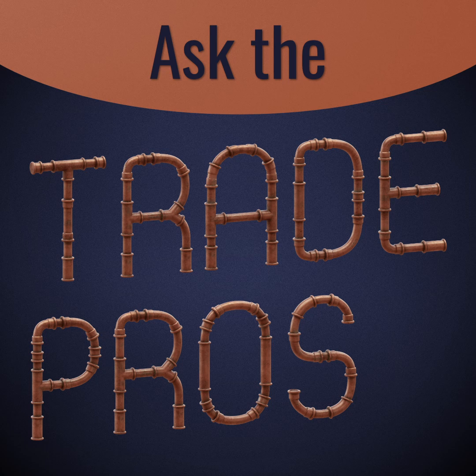So we strongly recommend that you be aware whether you have double taps. Don't do double taps. Make sure these breakers are one line per breaker, because that's exactly how they're sized. Let's talk a little bit more about other things to do with the panel.